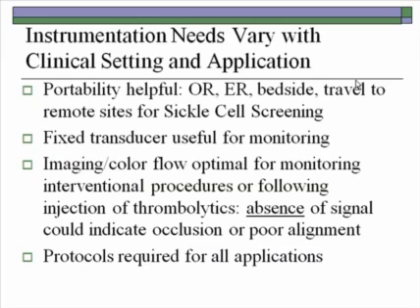The instrumentation needs will vary with the clinical setting and the application. Portability is very helpful because you're often going to the operating room, the emergency room, or the patient's bedside, and in some cases you can travel to remote clinical sites for sickle cell screening. A fixed transducer is useful for monitoring, allowing you to attach the transducer to the patient's head using a headband and continuously monitor the middle cerebral artery. Imaging and color flow are optimal for monitoring interventional procedures or following the injection of thrombolytics. The absence of a signal could indicate occlusion or poor alignment, so imaging is optimal in those cases.